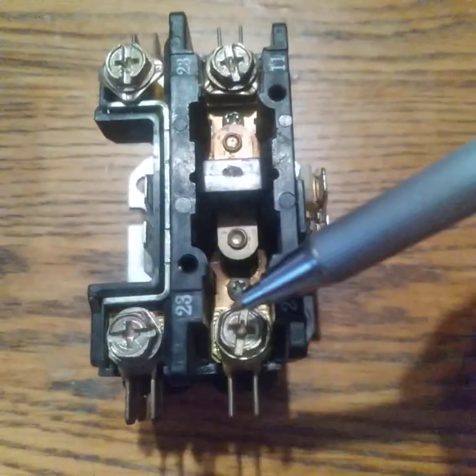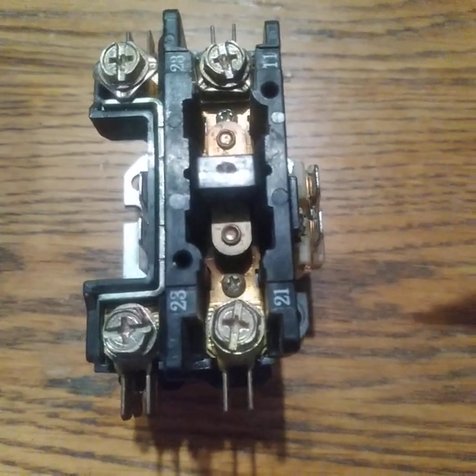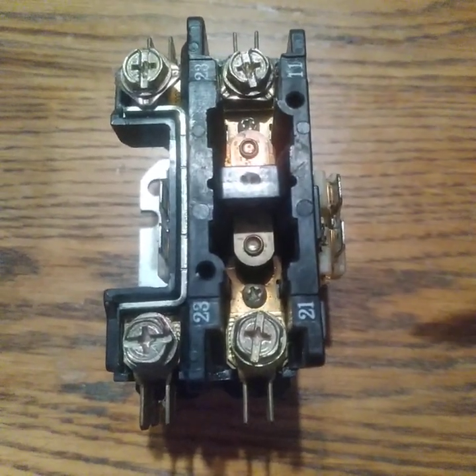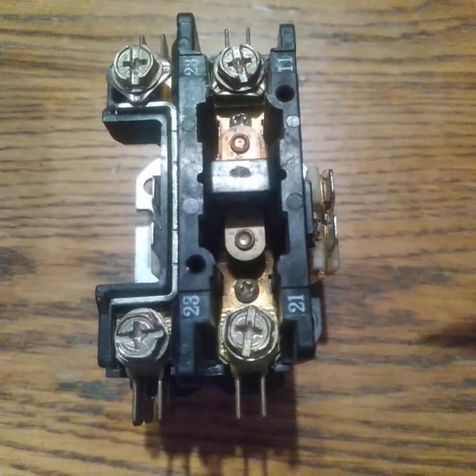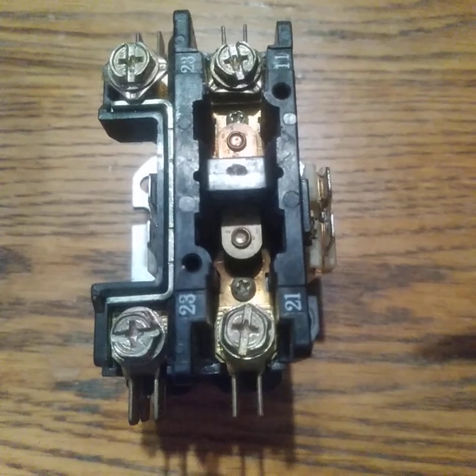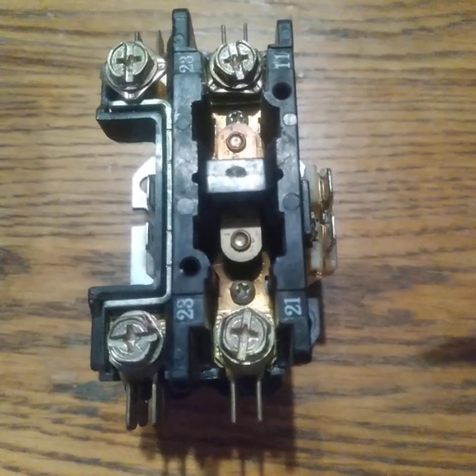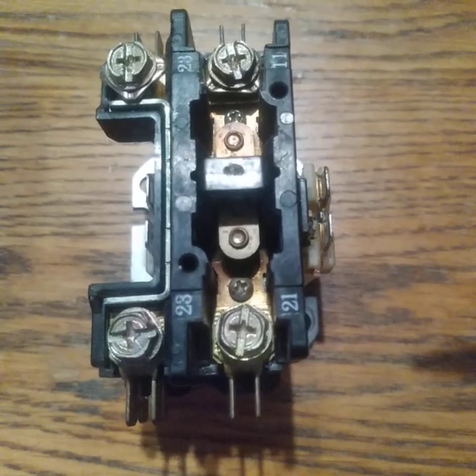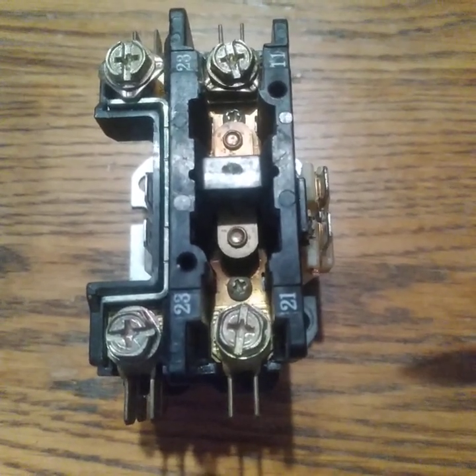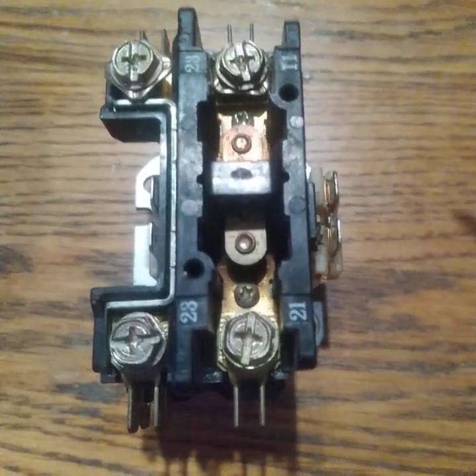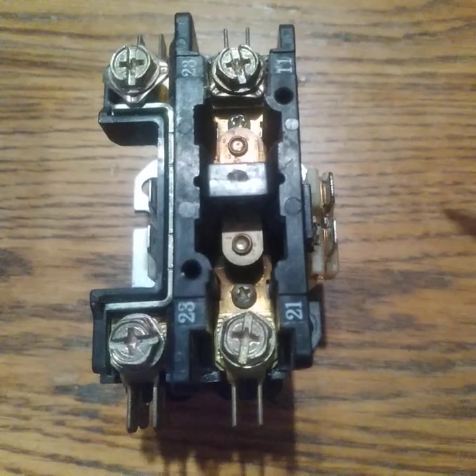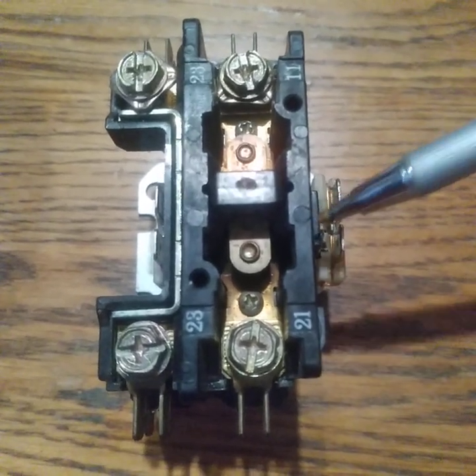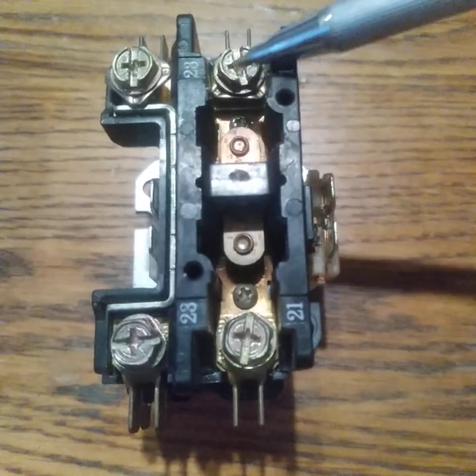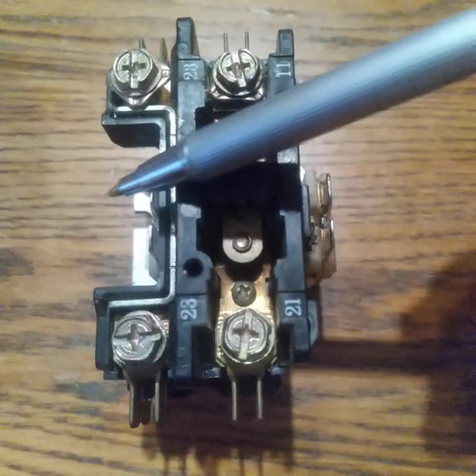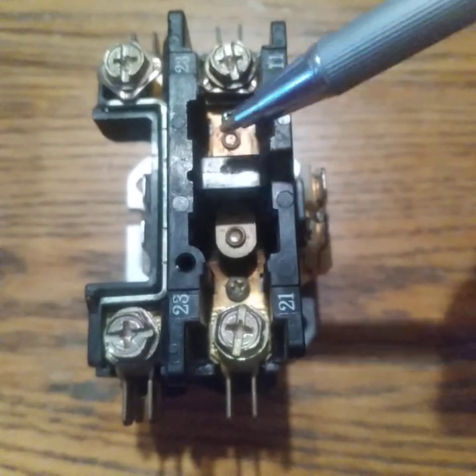Once you go from L1, L2 to T1, T2, at that point you have enough voltage to power up the compressor and the condenser fan motor. Once the thermostat in the house satisfies whatever temperature in the house and goes off, and the relay in the thermostat, we'll say hypothetically a relay, kicks off and opens, then this de-energizes and comes back up, and you don't have voltage here. But when the low voltage here energizes this, it pulls the contactor in, and then the voltage jumps here.